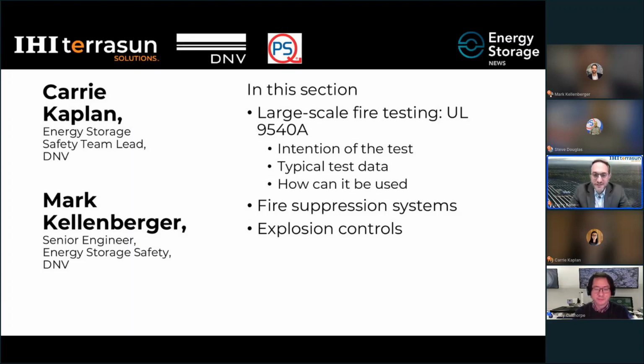Right. The different kinds of projects that we've integrated, standalone batteries, AC coupled and DC coupled with solar sites, really the focus is on the product with the battery and then the inverter. So from an overall safety perspective, as long as the products we use, the battery cabinet and the inverters, go through their individual testing. For the batteries, you still need to ensure that UL1973 testing is already done from the battery manufacturer, and UL1741 for the inverter manufacturer. Then what it really comes down to is the control system. And again, as I mentioned, that's where TerraSun works to build that specifically for the unique project at site and to meet our customers' exact needs.